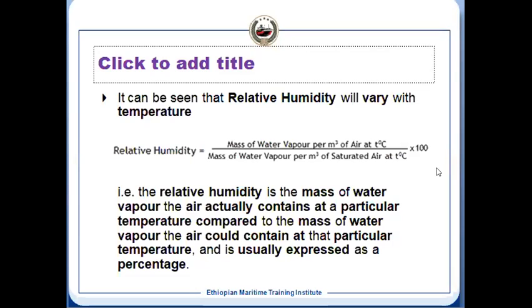First we have done the cooling and reached the desired temperature, but at that temperature, relative humidity has not reached our level. It means absolute humidity was the same. So by dehumidification, we reduce the absolute humidity, then reheat it to achieve the correct relative humidity level. Is it clear, Pekka?